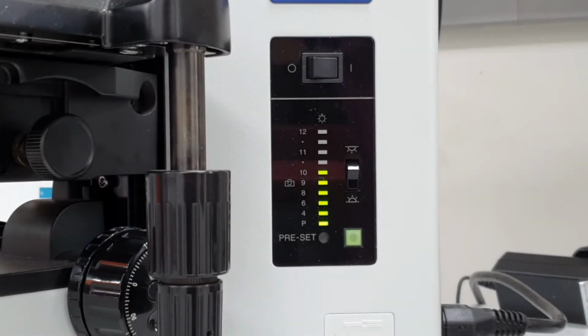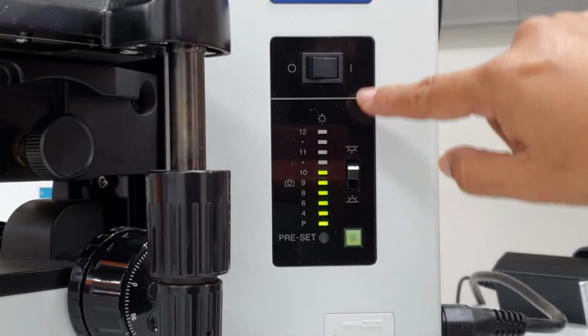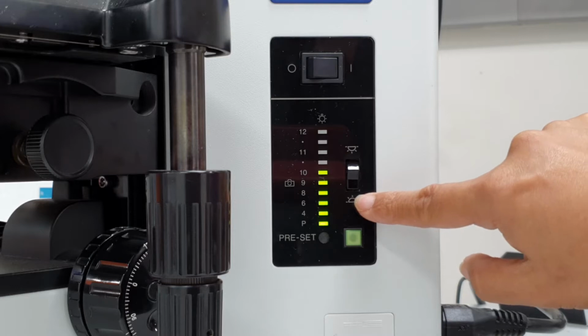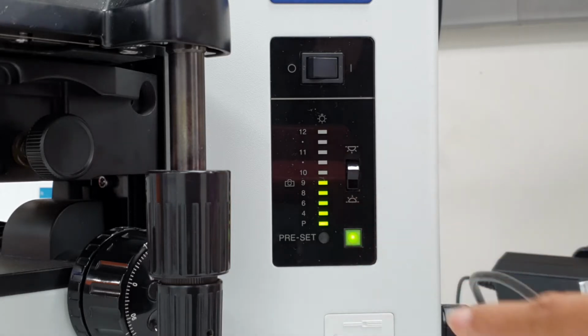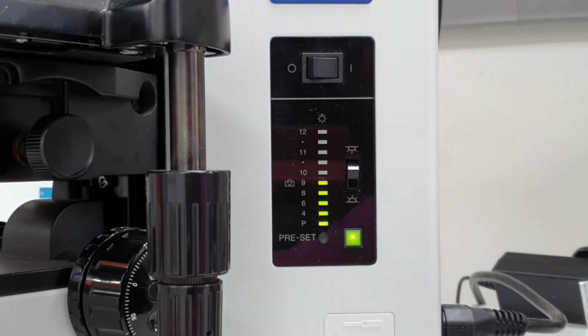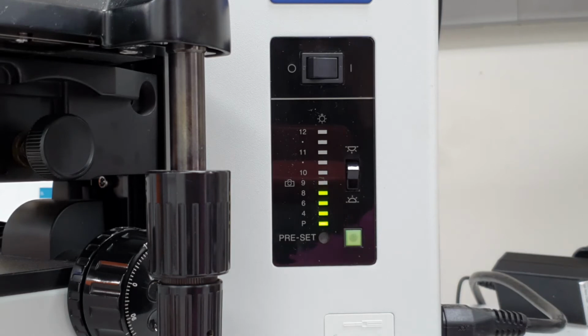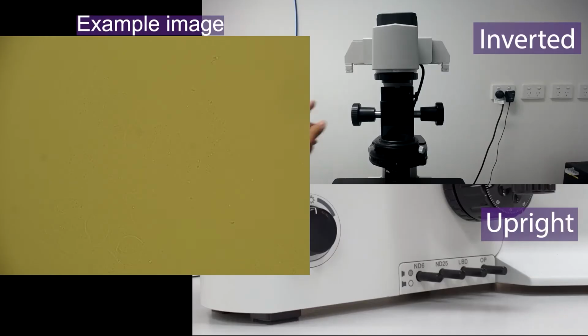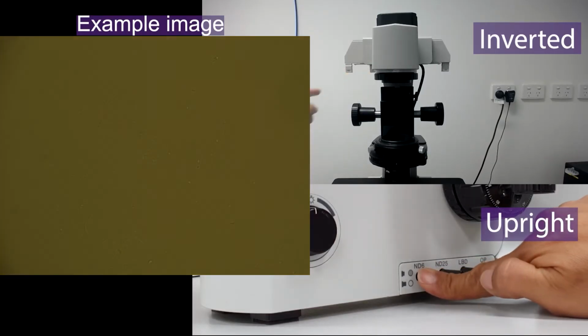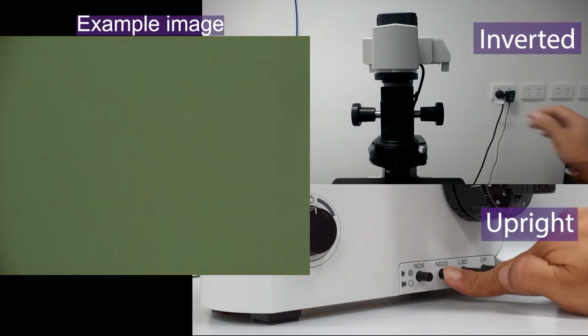To perform phase contrast imaging, first check that the lamp is on and the brightness level is acceptable to provide good contrast. On the upright stand, make sure the bottom lamp is on and the preset is off so that you can adjust the light intensity and that the bright level is suitable. Insert neutral density and color filters as required to achieve a good white balance background.